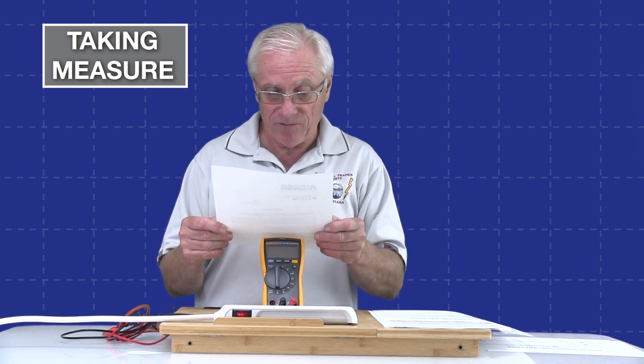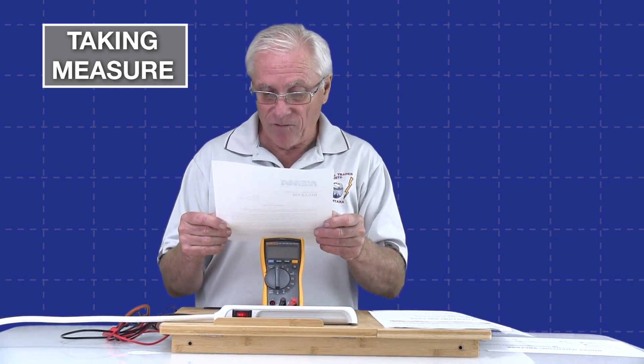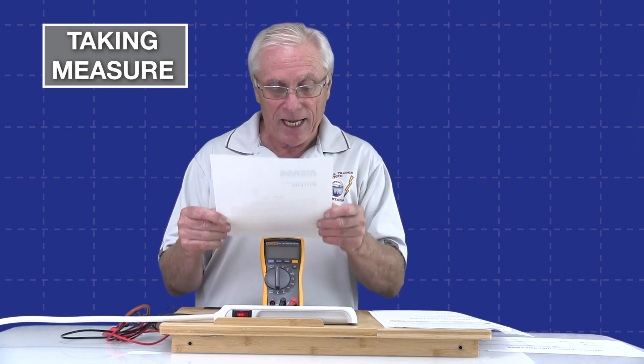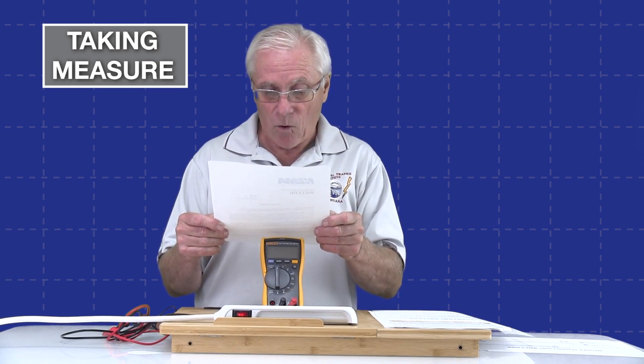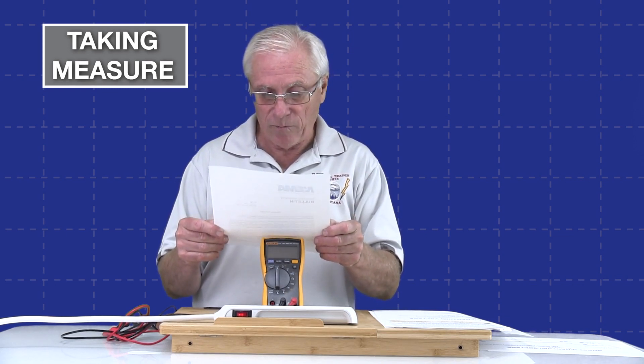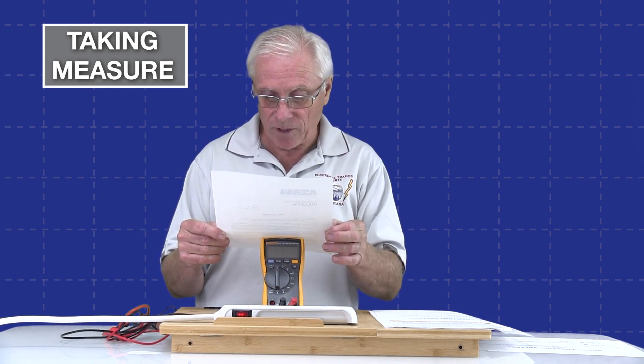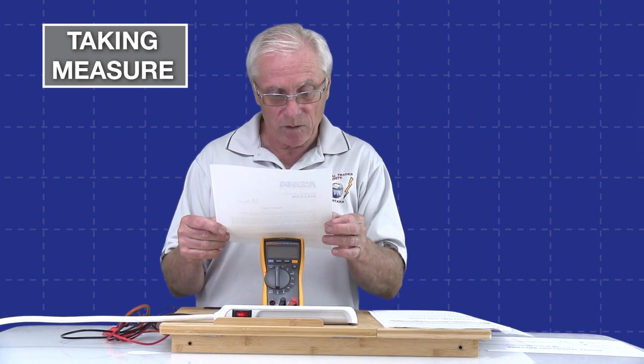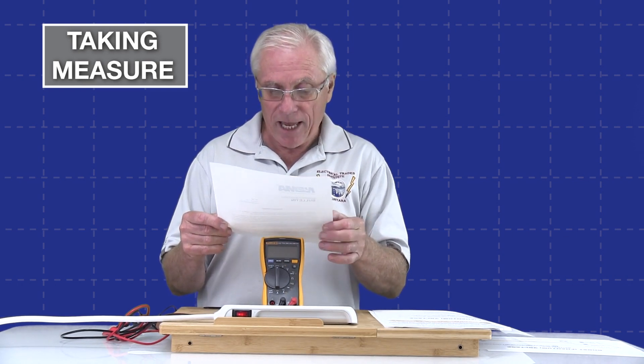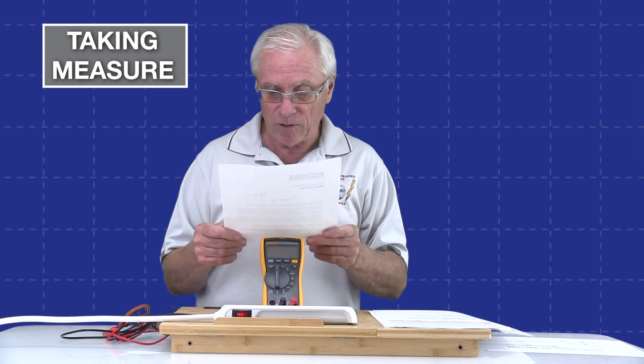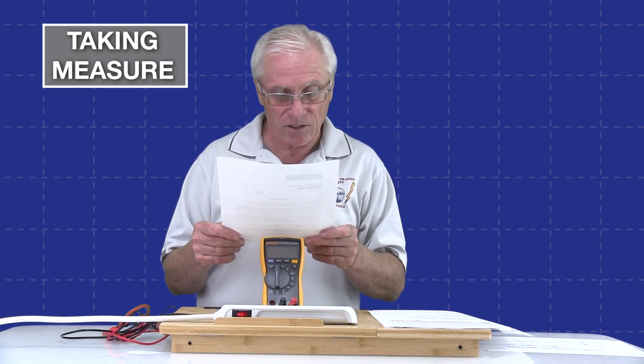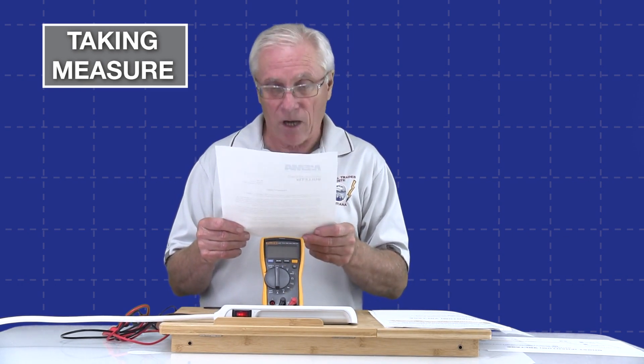Since the phantom voltage is a physical phenomenon involving very small values of capacitance, it cannot energize a load or cause physiological damage to a person. Care must be taken to be sure the voltage reading is a phantom voltage, which is caused by improper use of high impedance multimeters and not as a result of a cable defect or improper installation, which may result in a shock hazard.